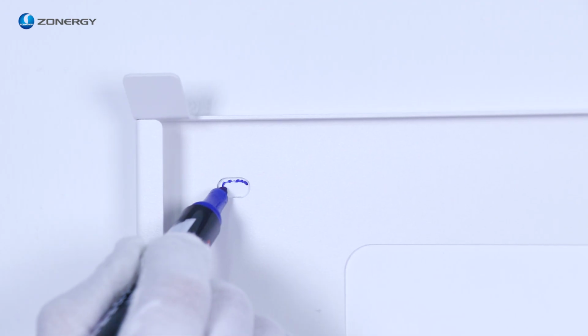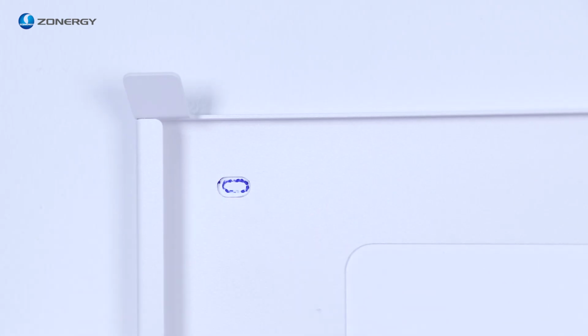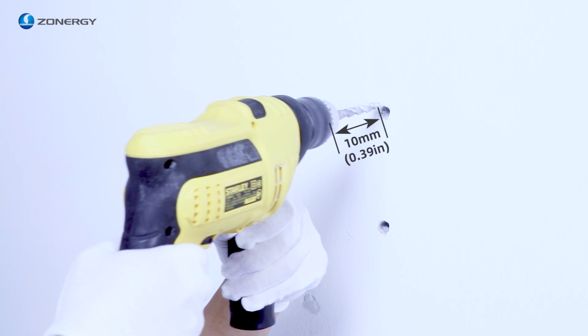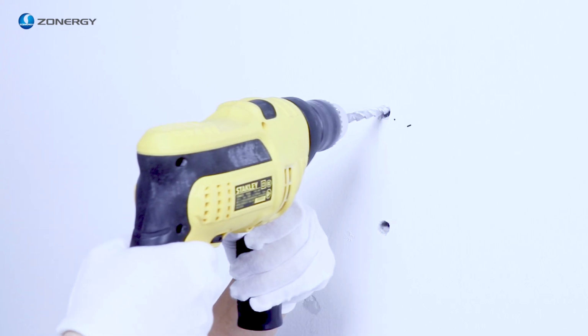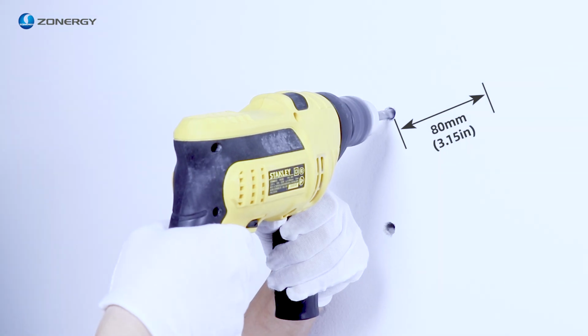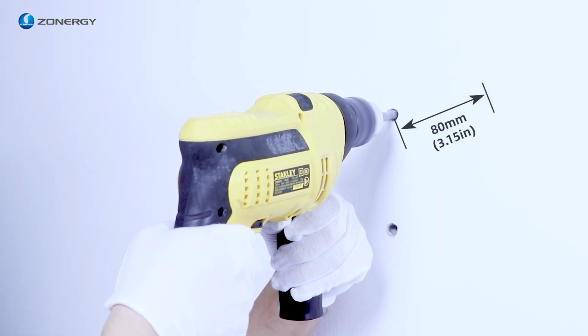Install the inverter. First, place the wall-mounted bracket horizontally on the wall and mark the corresponding points through the holes. Use a percussion drill with a bit diameter of 10 millimeters, 0.39 inches, to drill holes and ensure that the hole depth is about 80 millimeters, 3.15 inches.